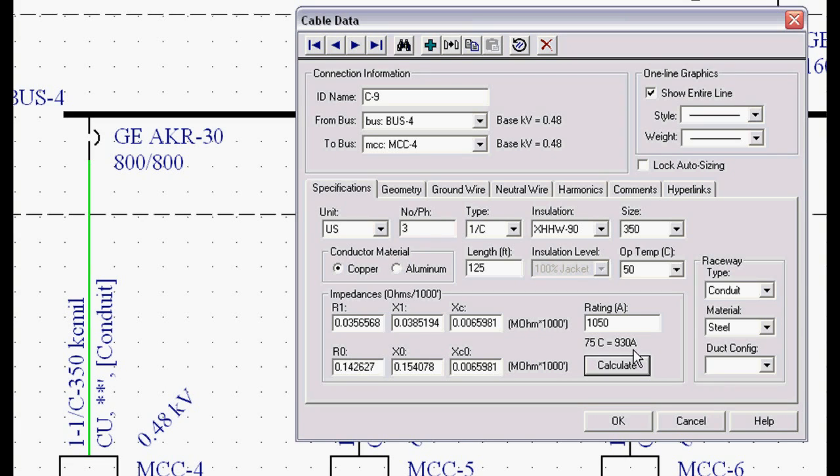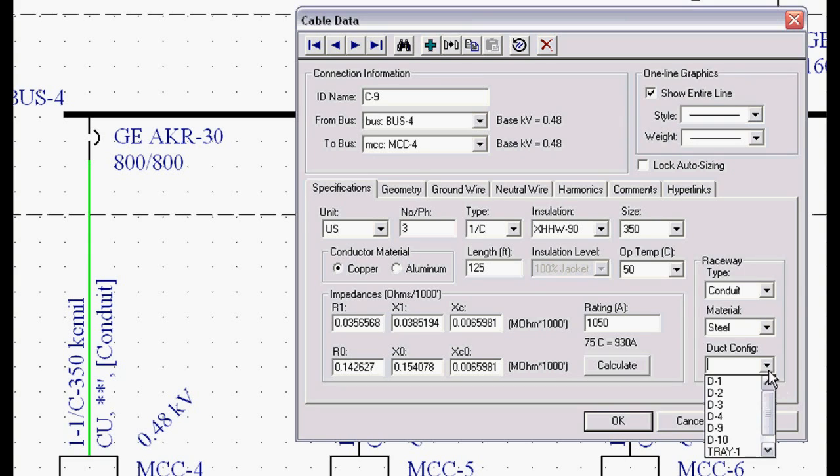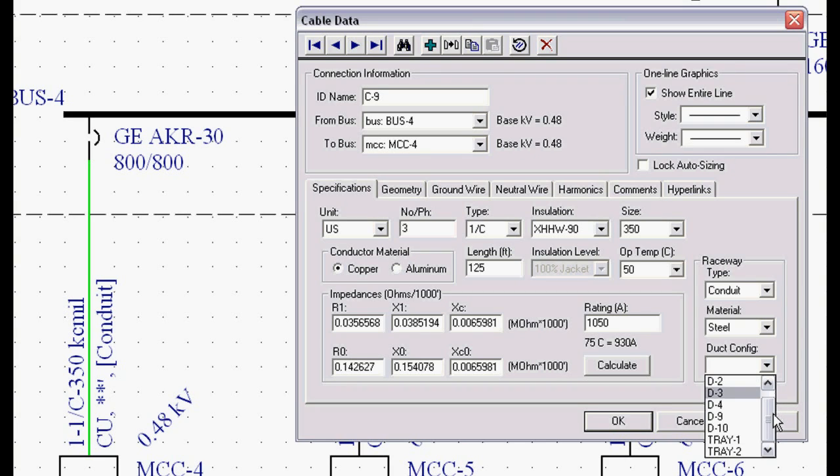It also derates for the 75 degree C terminal rating, which we use in all of our design work. We can derate further by any different type of duct bank configuration. This is all customizable, number of fill and tray and things like that.